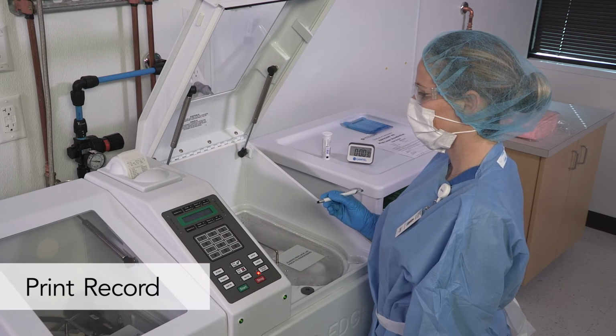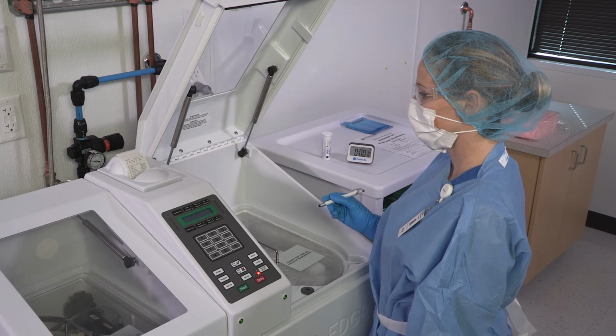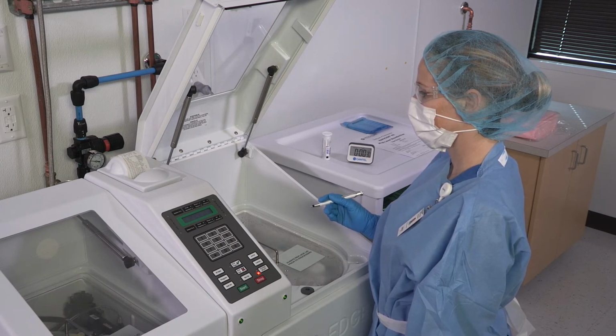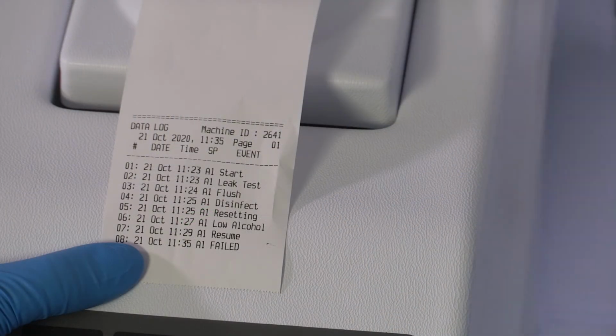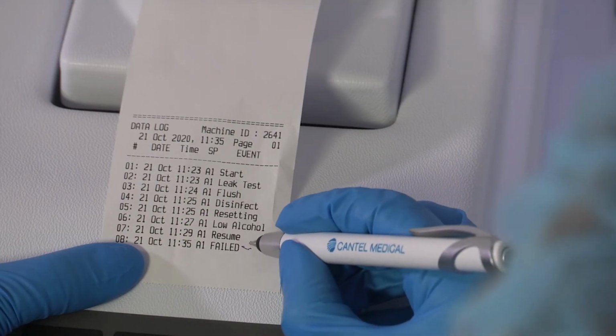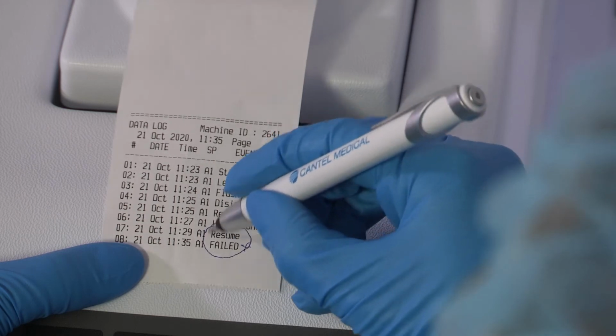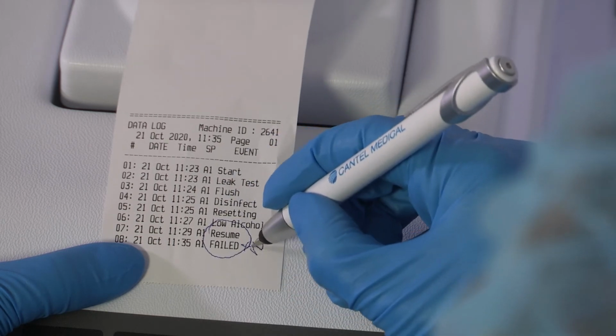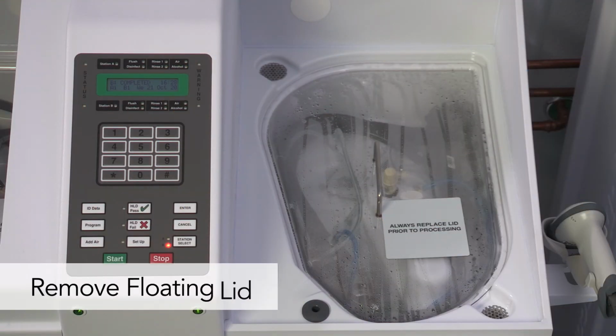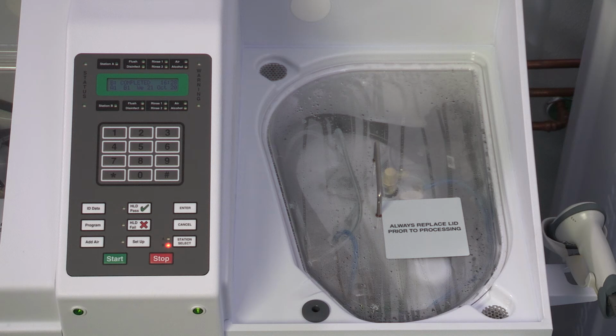The DSD EDGE Reprocessor automatically prints a record of the cycle, including the ID data, any error messages, HLD pass or fail with basin temperature of the disinfectant, and a cycle complete or cycle aborted message. Check to see if there is fluid on top of the floating lid at the end of the cycle. Any fluid should be discarded through the basin and the cycle repeated.